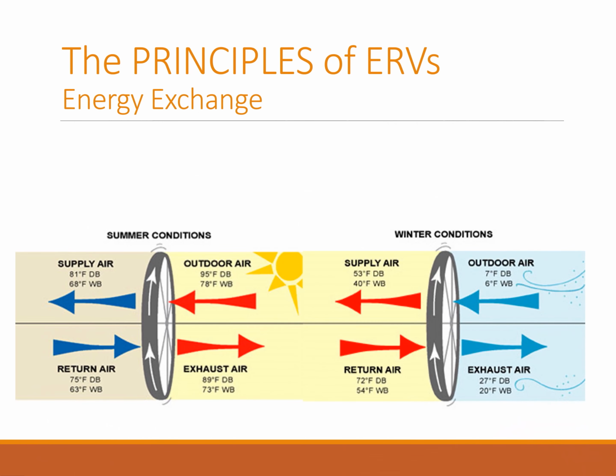Let's take a look at this wheel example. In summer conditions, the OA has a 95-degree dry bulb or 78-degree wet bulb condition. The return air comes back from the system at 75 degrees dry bulb and 63 degrees wet bulb. The impact of the ERV and its energy recovery can be seen in the SA, or supply air quadrant, with an 81 degrees dry bulb and 68 degrees wet bulb temperature.